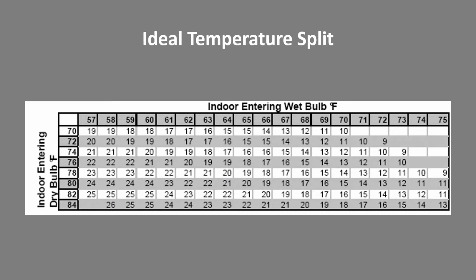It's working just fine. And for large parts of the year in the Northwest climate, that's true. Say we have an indoor dry bulb going into the indoor coil at 76, and the indoor wet bulb is 62. Yep, guess what? You have the ideal temperature split.